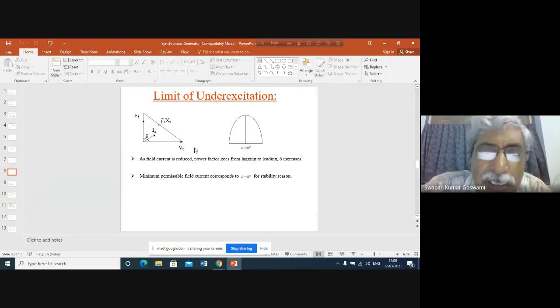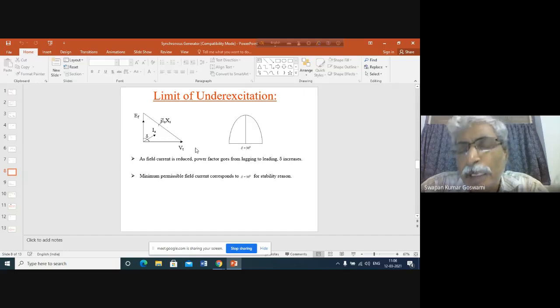I am saying that actually, when the load is high, demand is heavy during daytime and during the early night, so there is demand for active power, and whenever there is demand for active power, there is demand for reactive power as well. In the load curve, we don't show that, we show only the active power demand. But in general, you can say that the power factor of the load connected to the system may be 0.8, 0.85. This is the average power factor. So you may calculate what is the reactive power demand. As soon as the active power demand is known, you will know how much the reactive power will be.